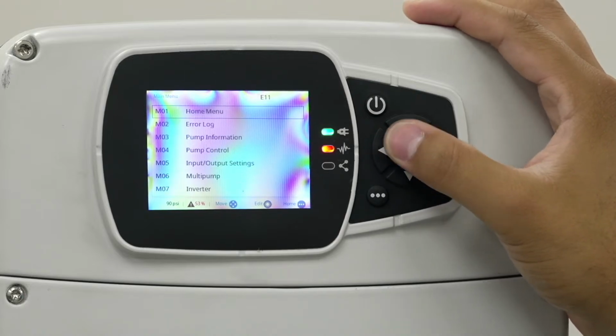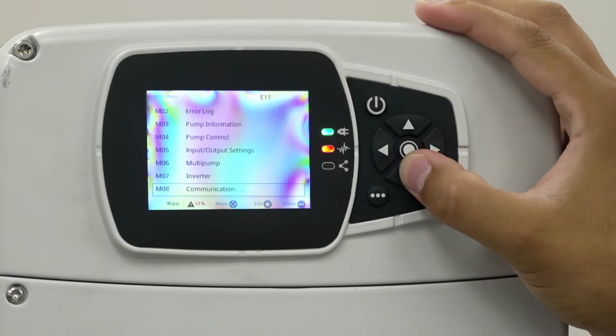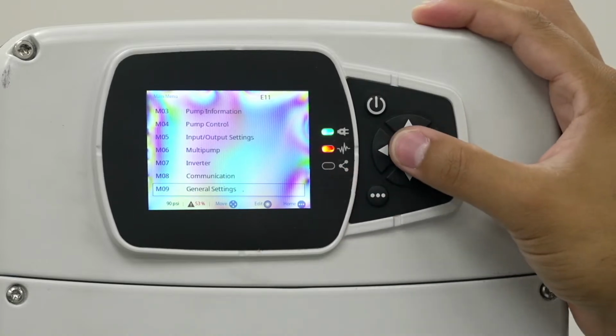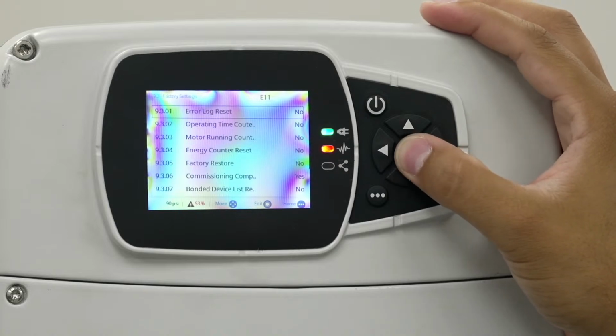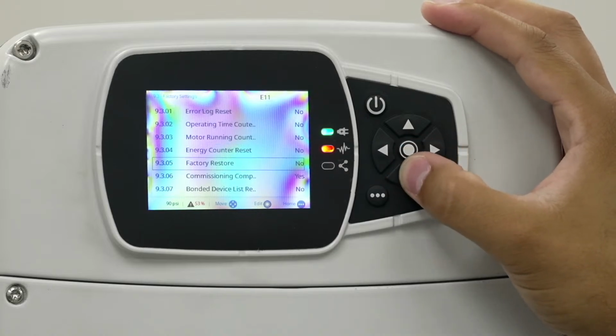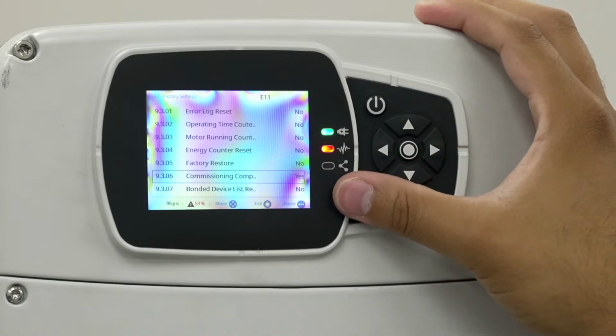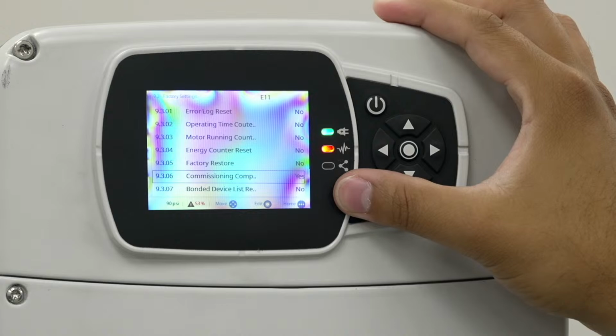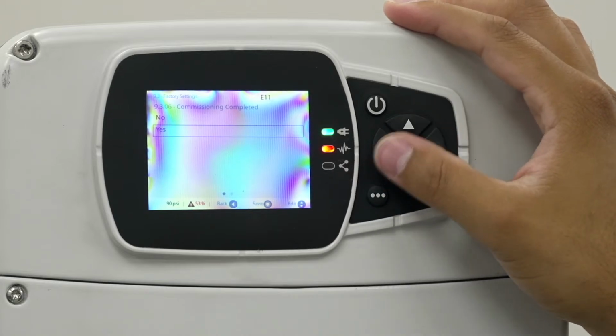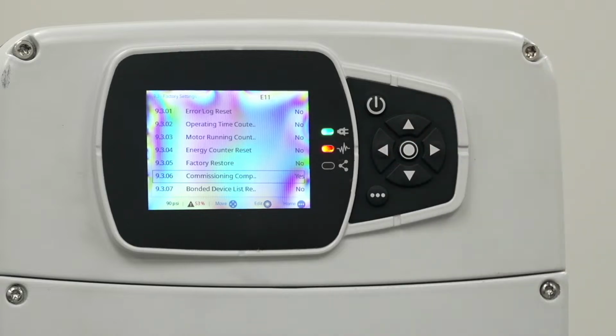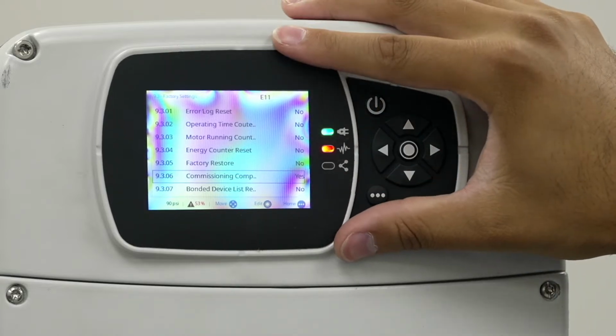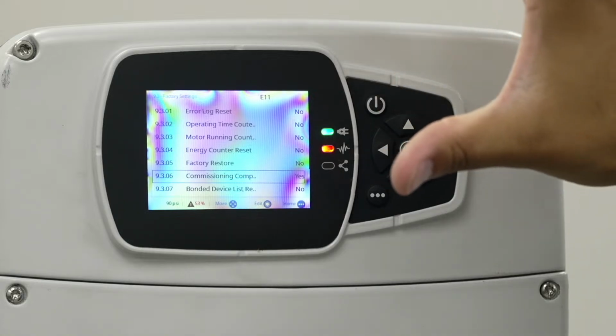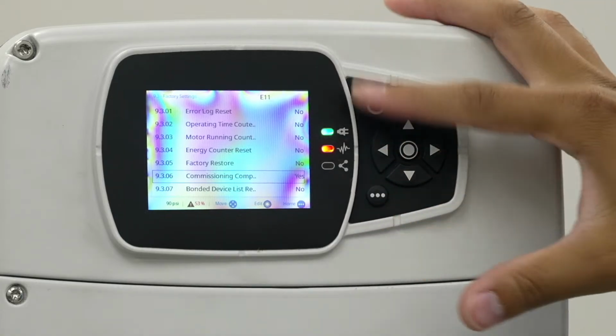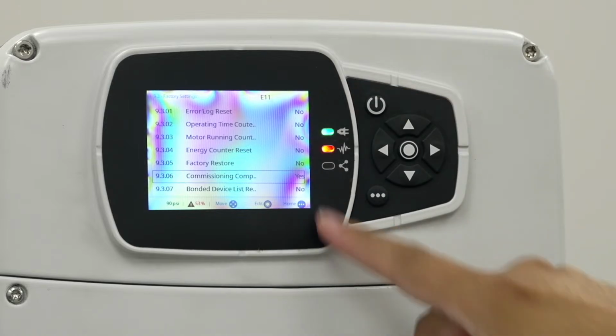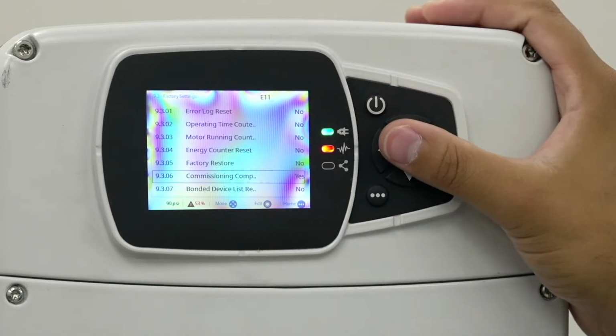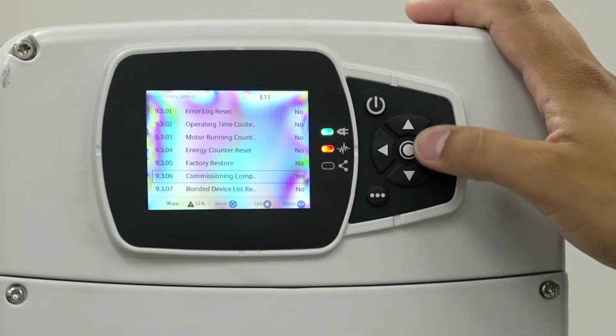If you truly just wanted to start over and go through the Genie again, what you would have to do is once again go down to General Settings, Factory Settings, and there's something called Commissioning Complete. So right now it says yes. That is because I went through the Genie and completed that. I would go into there, change it to no, and once I switch it to no, I would have to cycle power to the unit, and upon powering back up, that Genie would ask me if I want to go back to the Genie. If you simply cycle power without switching this to no, it's just going to go right back to the home screen because it understood that you've already set the parameters to the Genie.